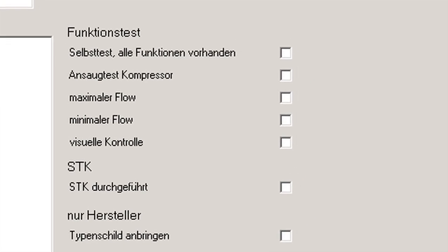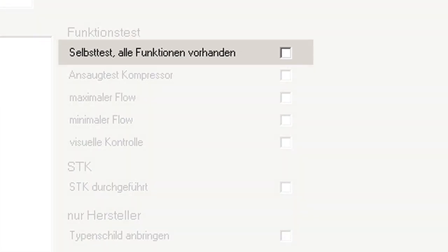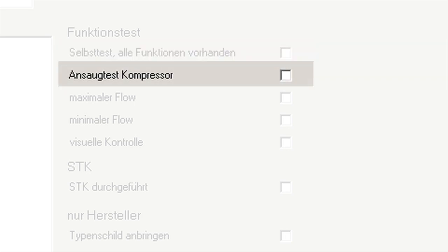During a self-test, the device turns itself on and reviews whether or not the necessary internal device functions are running correctly. If no errors are shown on the LCD display of the oxygen concentrator, the test has been passed successfully. During the compressor intake test, the intake opening behind the service cover will be sealed and the hoses will be checked for leaks acoustically.